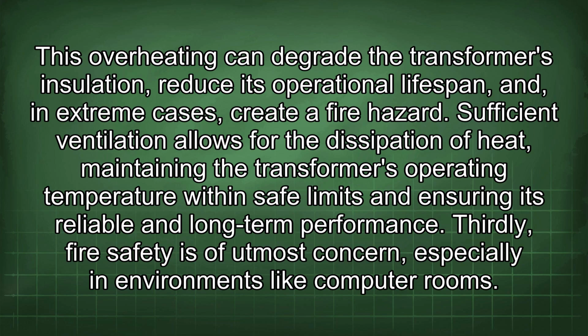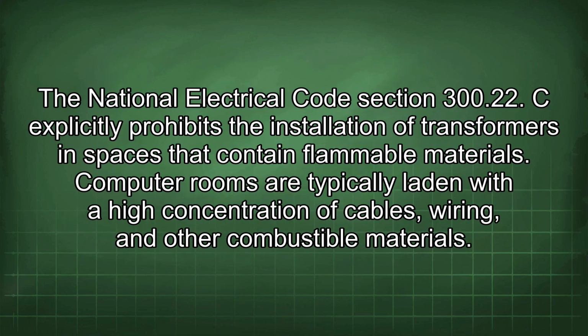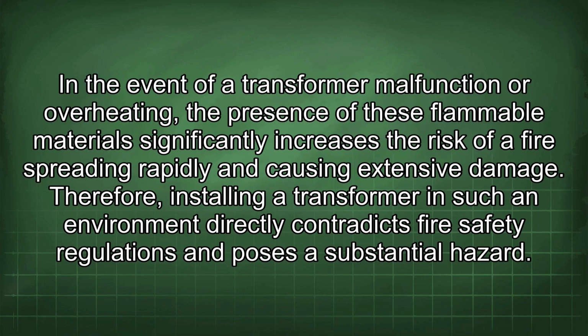Thirdly, fire safety is of utmost concern, especially in environments like computer rooms. The National Electrical Code Section 300.22(c) explicitly prohibits the installation of transformers in spaces that contain flammable materials. Computer rooms are typically laden with a high concentration of cables, wiring, and other combustible materials. In the event of a transformer malfunction or overheating, the presence of these flammable materials significantly increases the risk of a fire spreading rapidly and causing extensive damage. Therefore, installing a transformer in such an environment directly contradicts fire safety regulations and poses a substantial hazard.